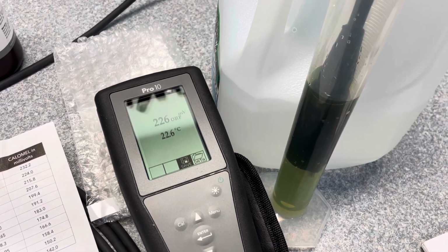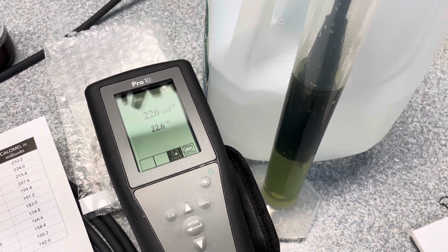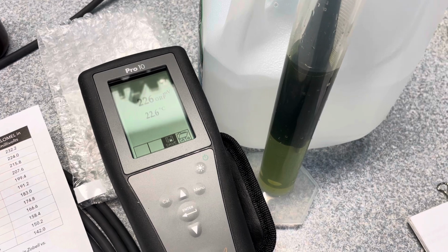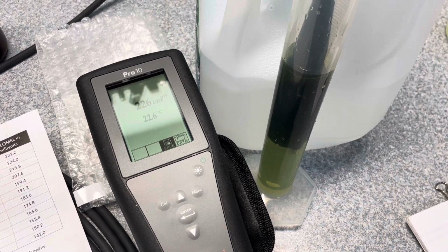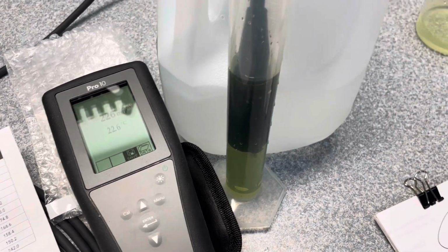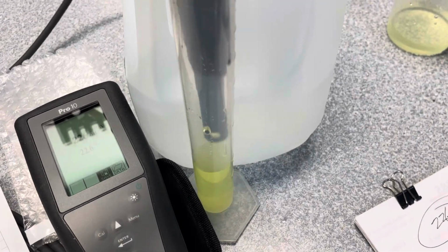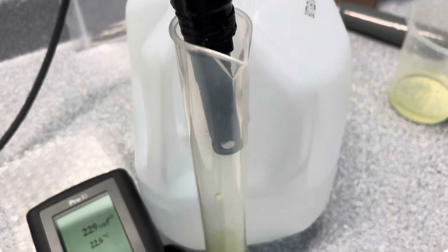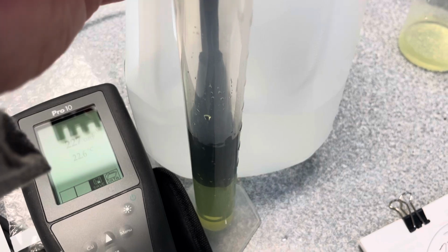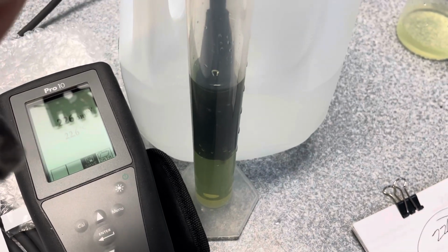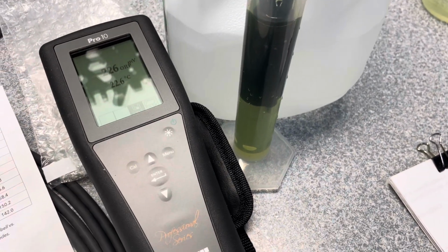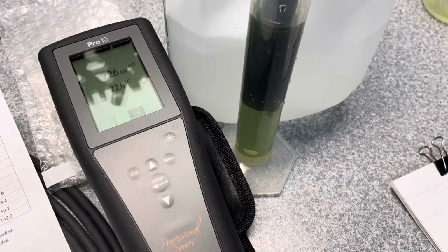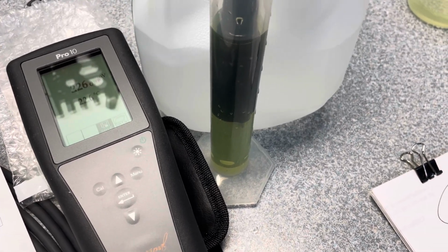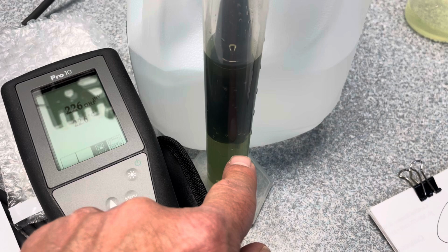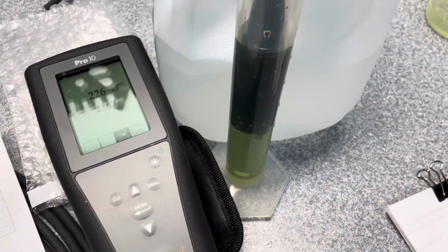I'm going to walk you through how to do a calibration on a YSI Pro 10 with the ORP sensor. Right now we have the ORP sensor on the probe. We rinsed it with DI water and then we rinsed it with some fresh Zobell solution, and we have it sitting in fresh Zobell solution right now, making sure that the temperature sensor is covered.